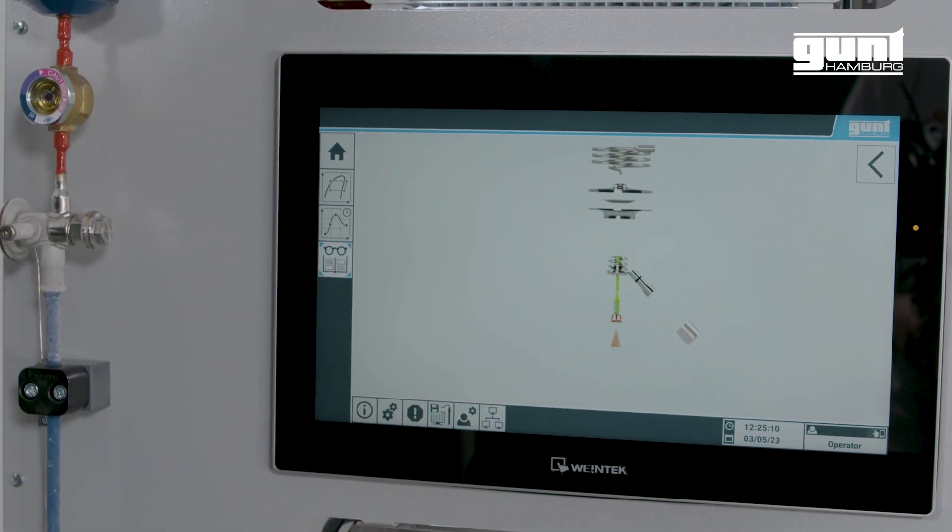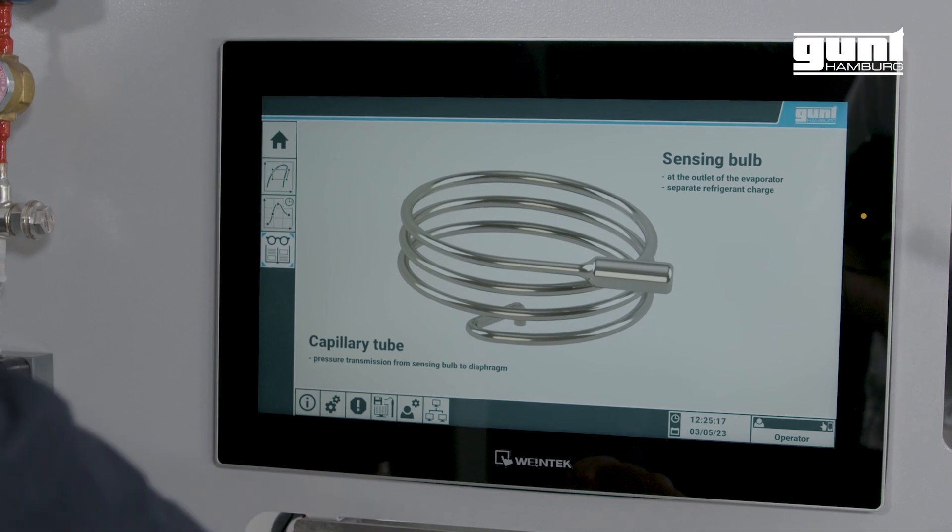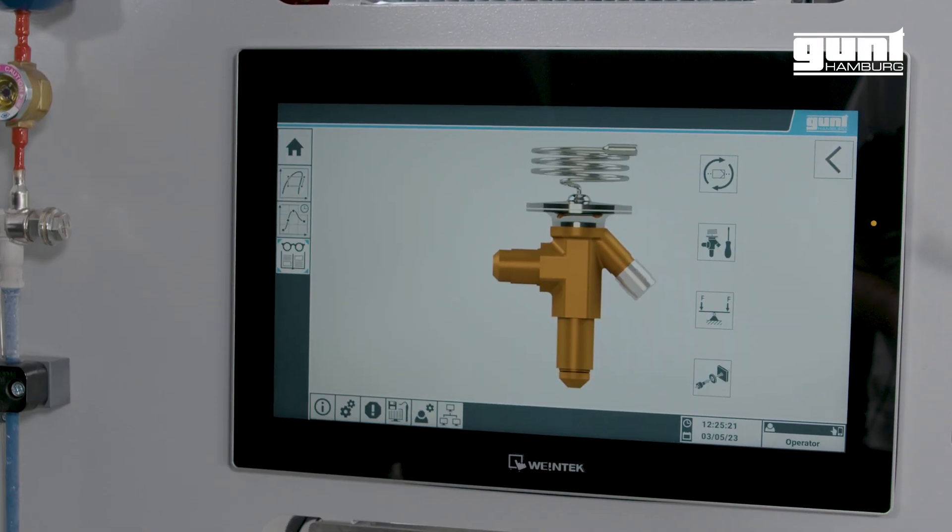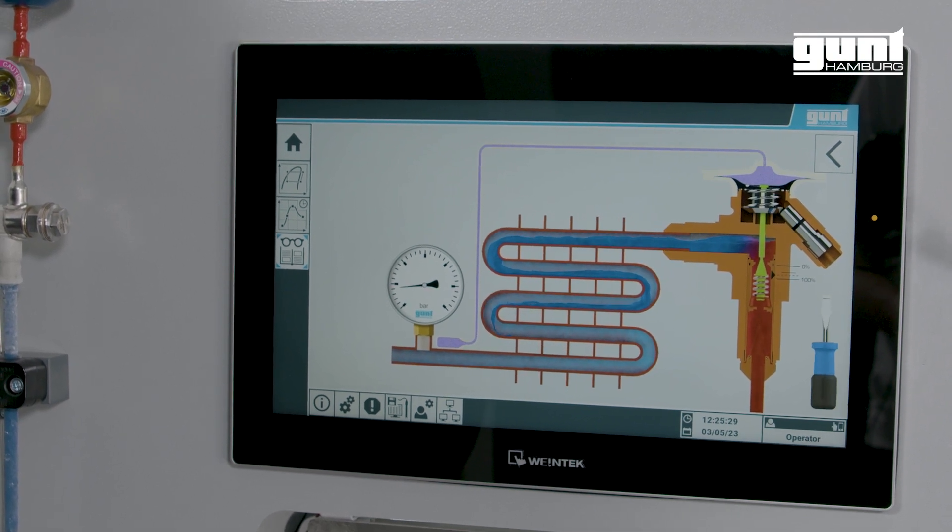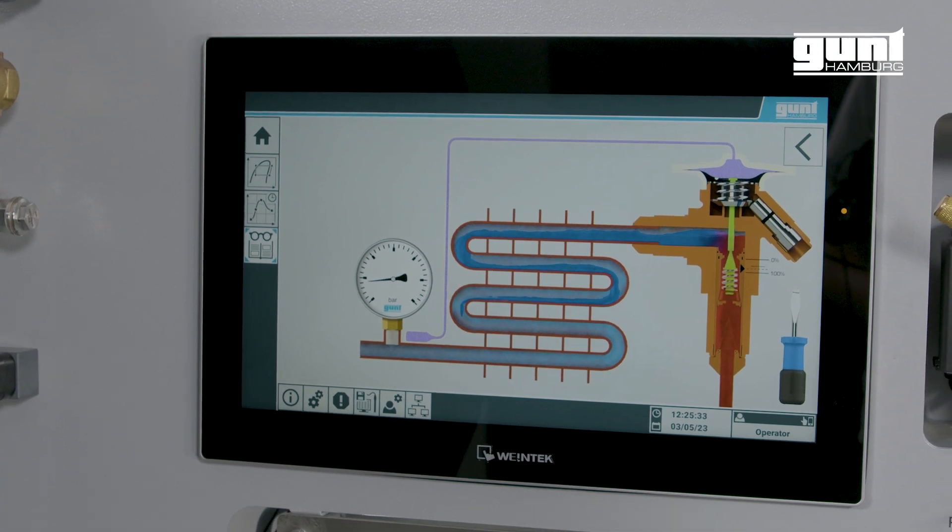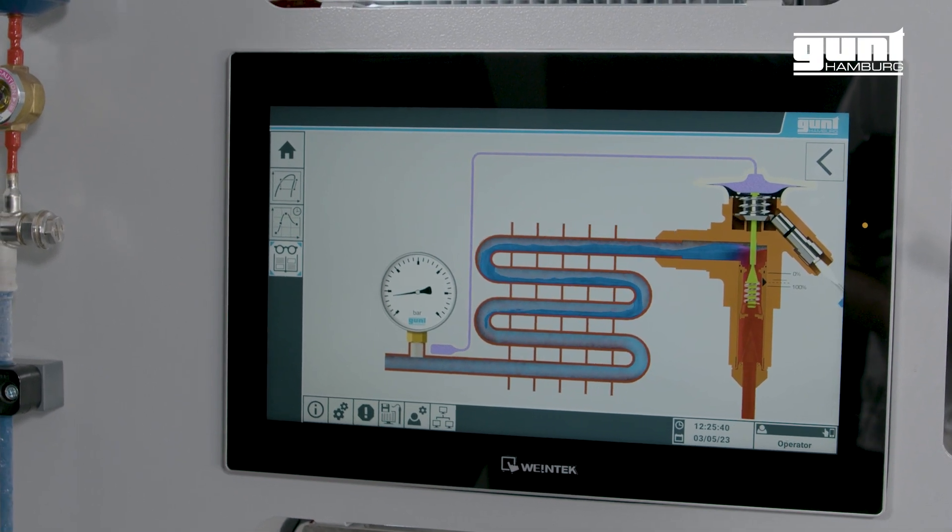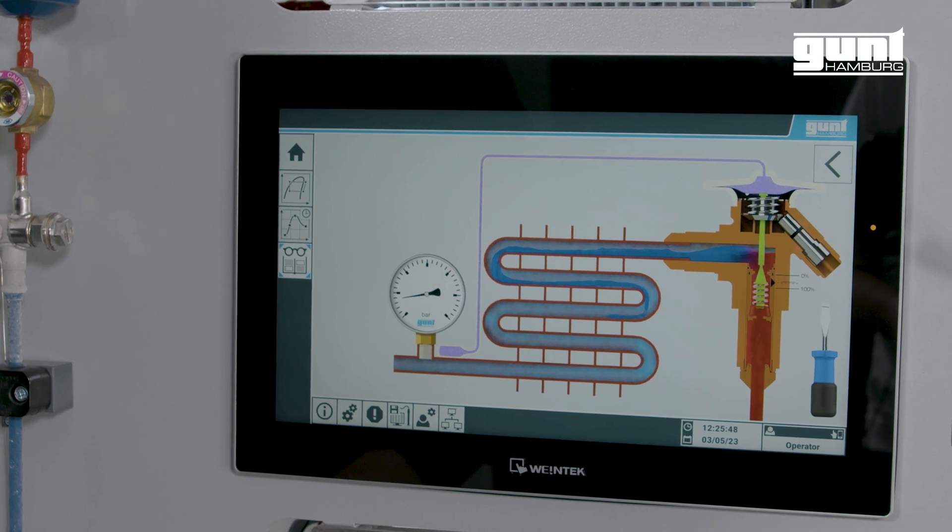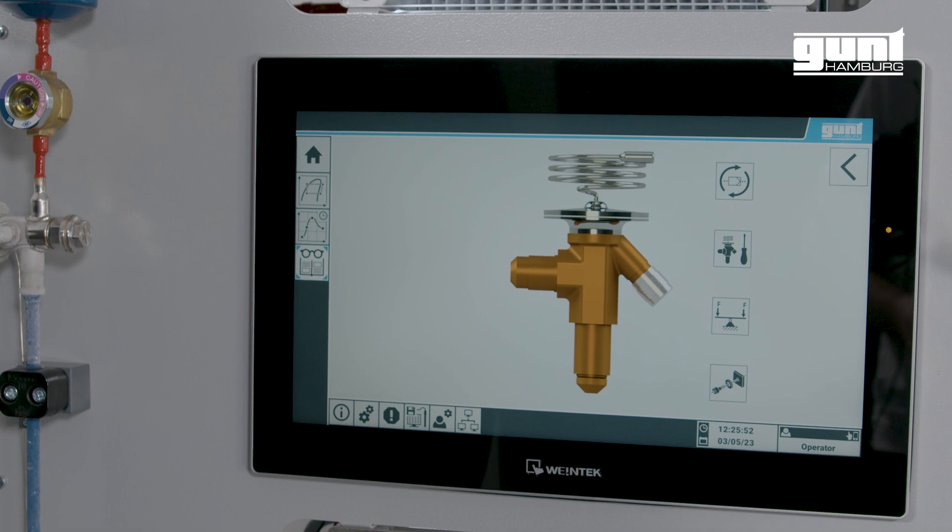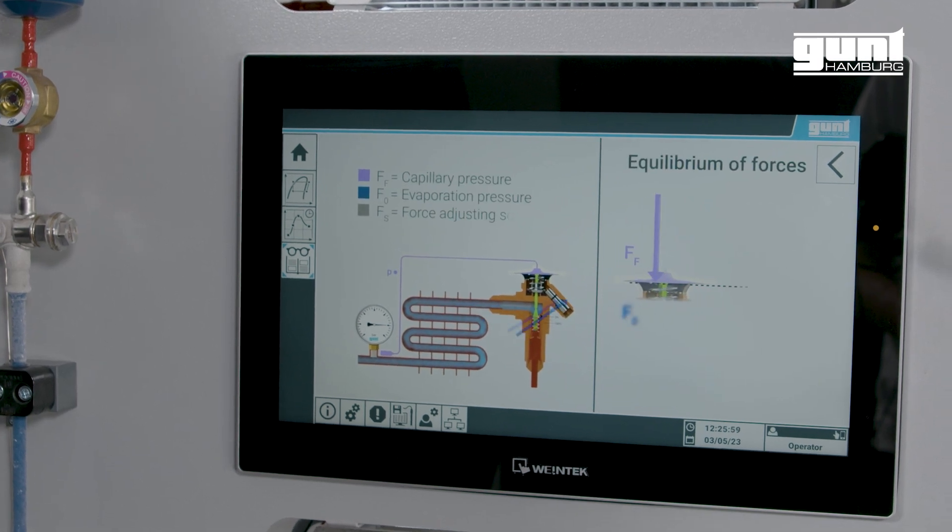And finally let's have a look at the expansion valve. Here we can see the individual parts and assemblies in an exploded view and get information about their function. Then we will take a look at the adjusting screw. Many people think that the mass flow is regulated by the expansion valve. However, this is not entirely correct. In fact, the only thing we adjust is the degree of the superheat, which determines how much the evaporator is loaded for the actual evaporation. The mass flow is determined by the thermal load and the available surface area of the evaporation.